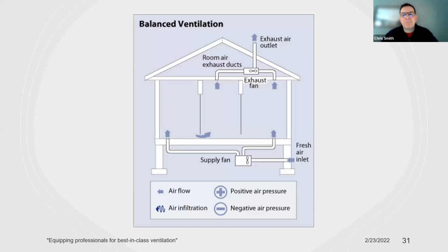Balanced ventilation uses a combination of exhaust and supply fans. And so now you're not necessarily relying on infiltration or exfiltration at all, but you can control the negative and positive pressure differential using your fans. And so you just get better quality control over your indoor air ventilation using a balanced mechanical ventilation system. This is good for the building.